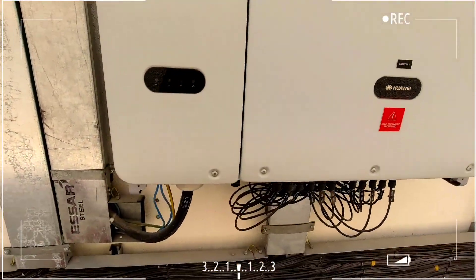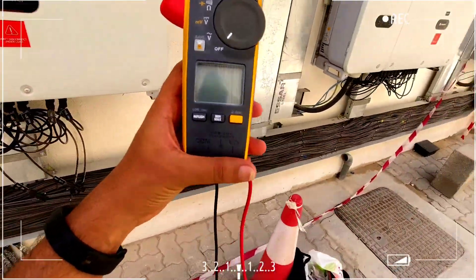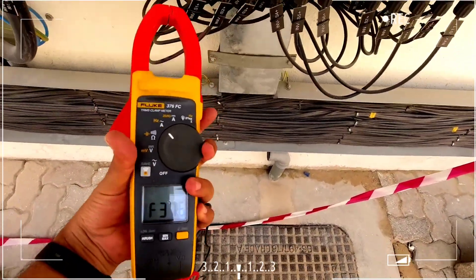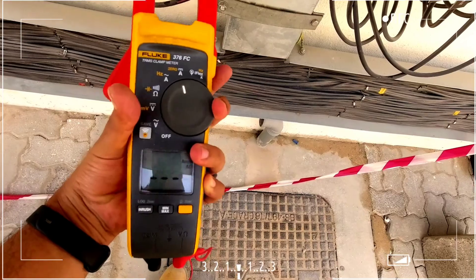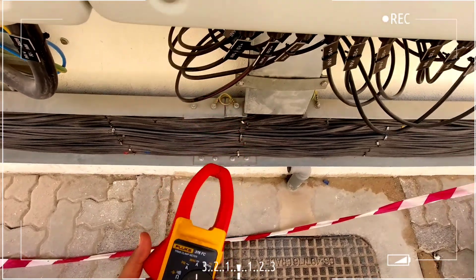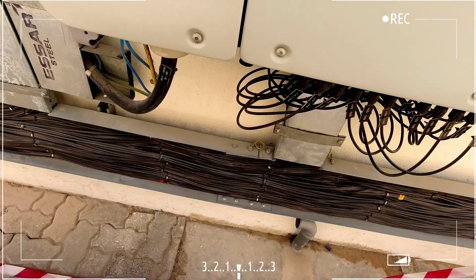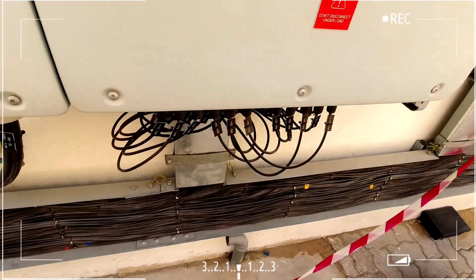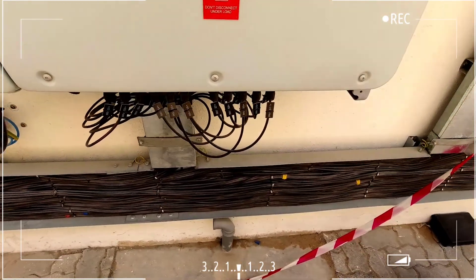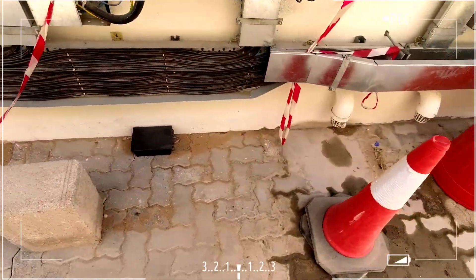As an O&M engineer, when you come to site your most important tool is the clamp meter. But to check this inverter, just in case you don't have a clamp meter or volt meter — you can see I've set it to DC amps and I'm getting around 6 amps. The best feature is that you can measure everything — current and voltage — using just a mobile phone and USB cable connected here.